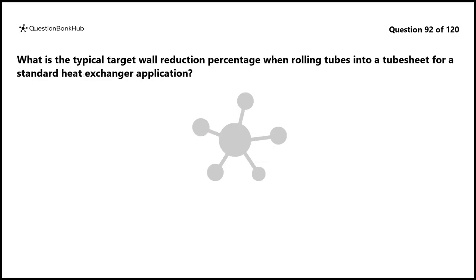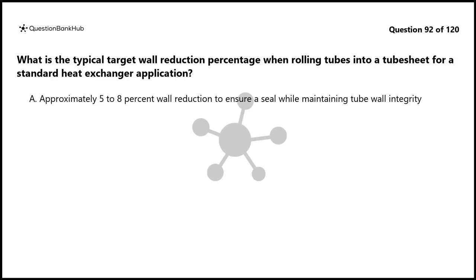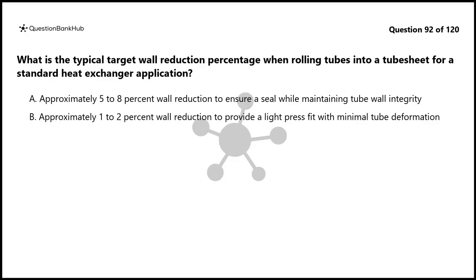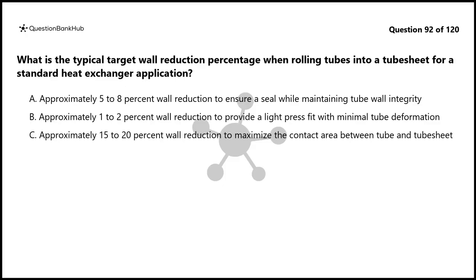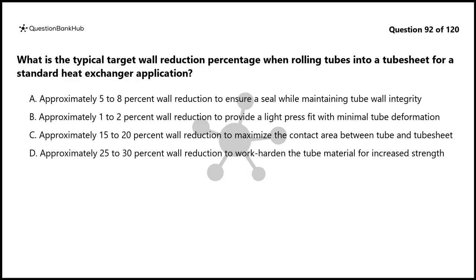Question 92. What is the typical target wall reduction percentage when rolling tubes into a tube sheet for a standard heat exchanger application? A. Approximately 5 to 8% wall reduction to ensure a seal while maintaining tube wall integrity. B. Approximately 1 to 2% wall reduction to provide a light press fit with minimal tube deformation. C. Approximately 15 to 20% wall reduction to maximize the contact area between tube and tube sheet. D. Approximately 25 to 30% wall reduction to work harden the tube material for increased strength.